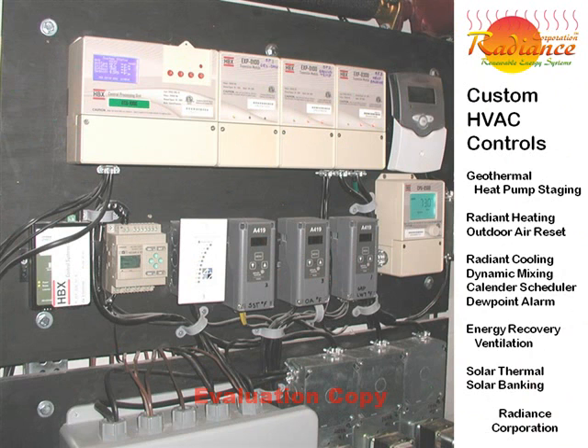Radiance Corporation designed a control system that leverages several energy-efficient control strategies. First, the geothermal heat pump is staged, so it operates at part load most of the time. An outdoor air reset control determines the lowest temperature water needed to heat the home in response to changing weather conditions. Cooling is locked out in cold weather and is only allowed by an automatic calendar scheduler.